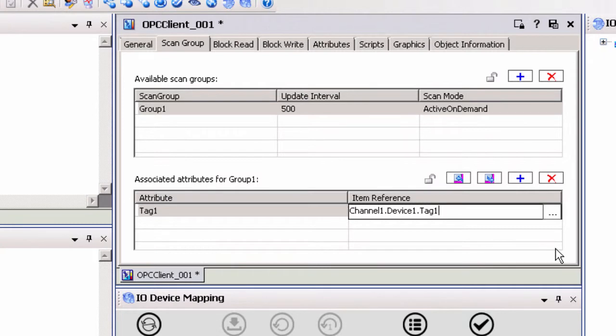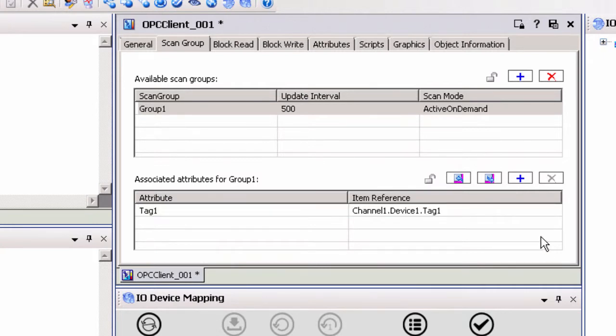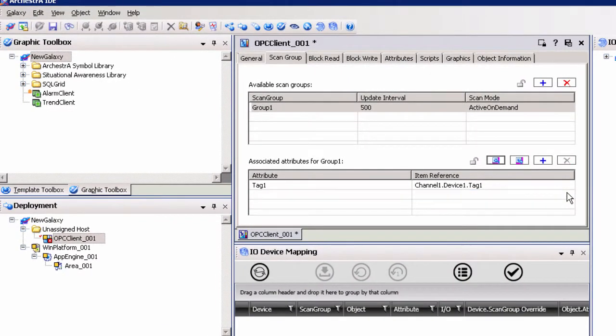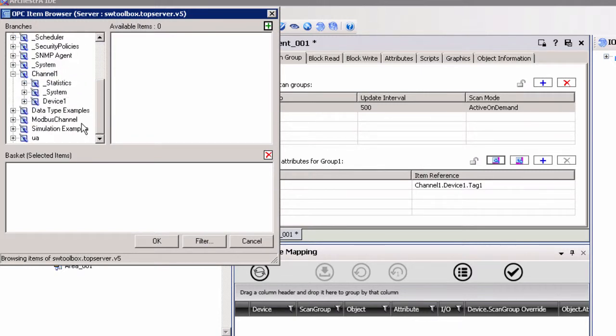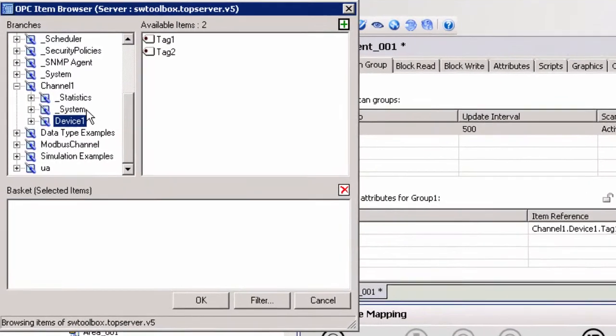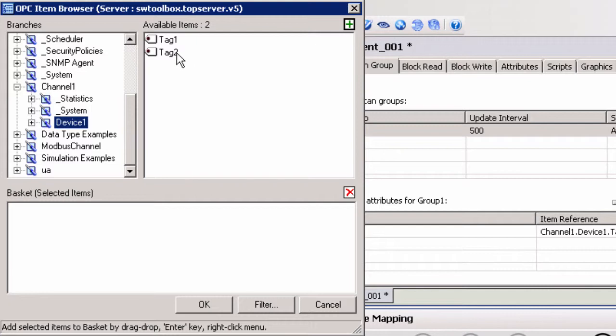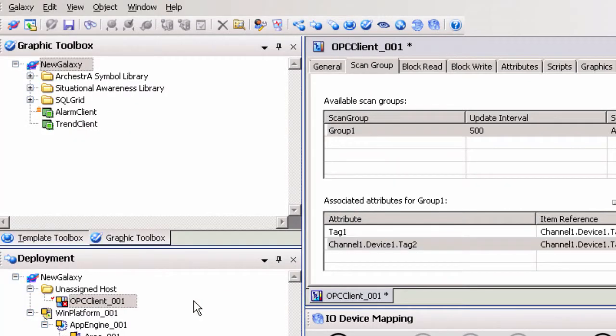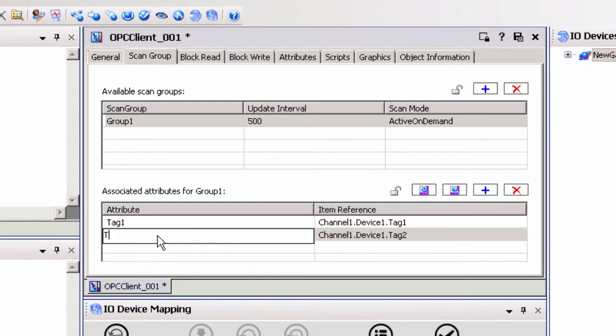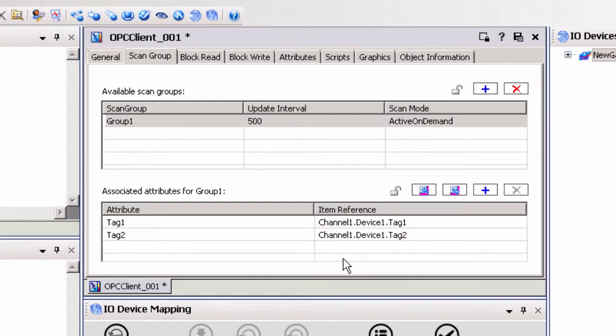You can either give the attribute a friendly name or leave it as the full address including the channel and device name from TopServer. We will call our attribute tag1. If static tags exist in TopServer, we can create the attributes by browsing to them in the TopServer tag database. Click the ellipses button to the right of the item reference column to open the OPC item browser. Expand channel1 and click on device1 to see the tags configured for this device. Select the desired items by dragging and dropping them to the basket area of the OPC item browser, then click OK to make these items associated attributes for the scan group. We will give this attribute a friendly name of tag2.